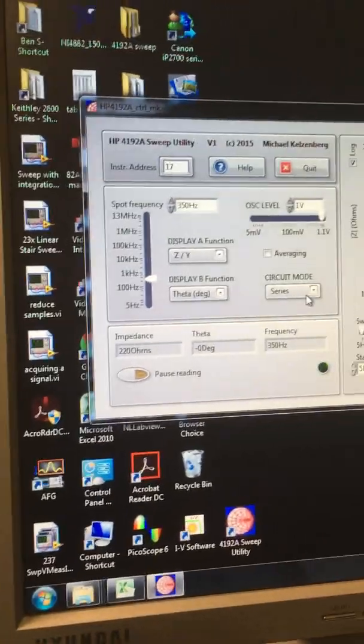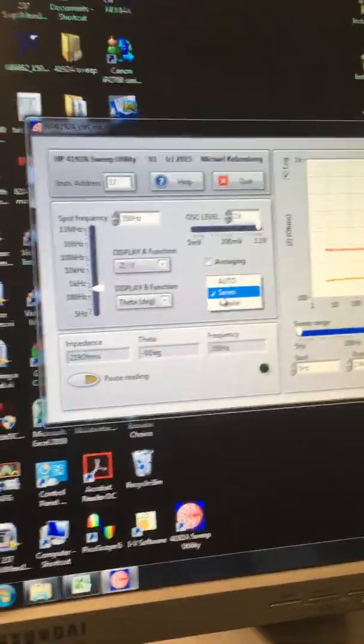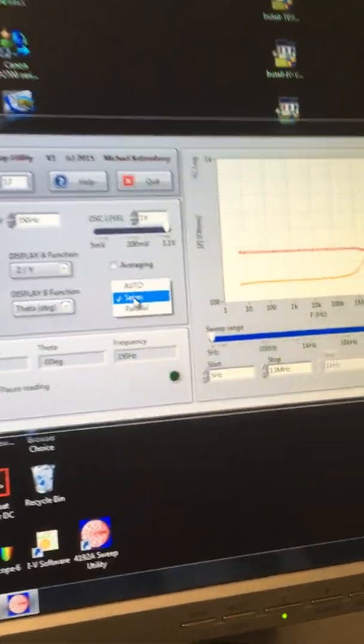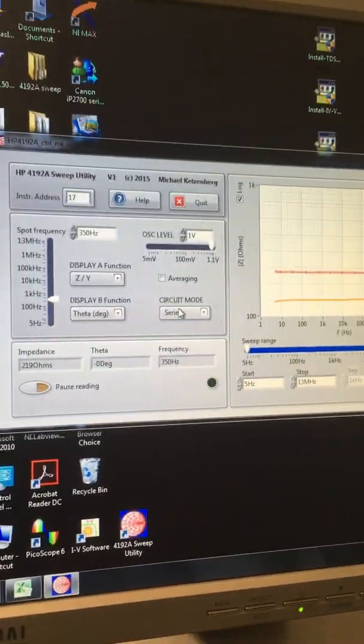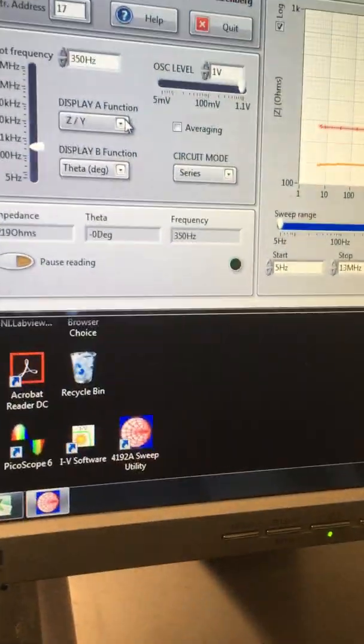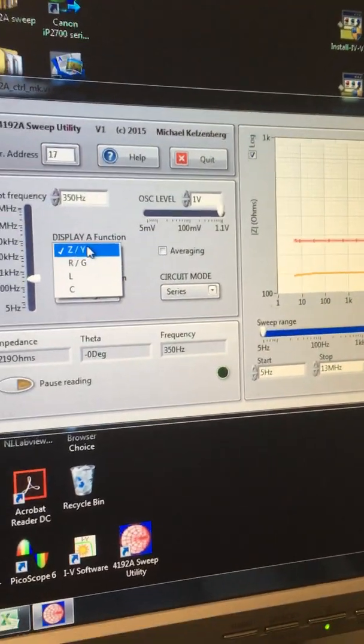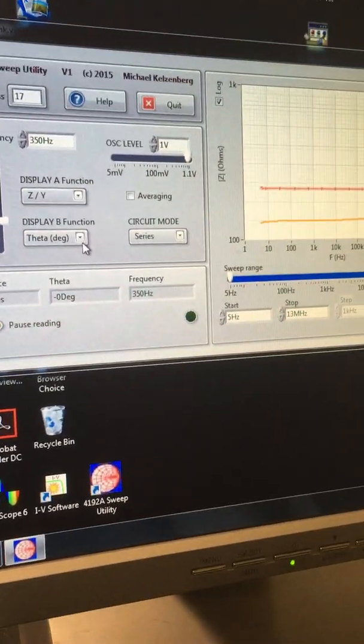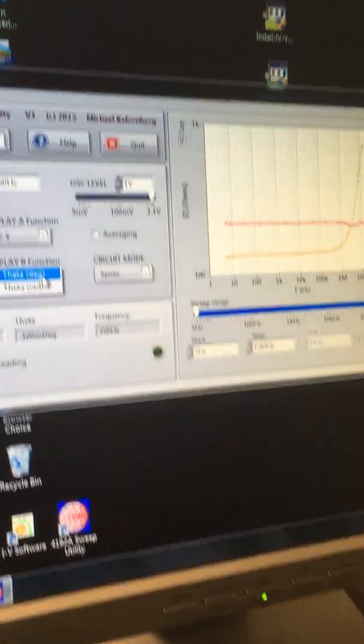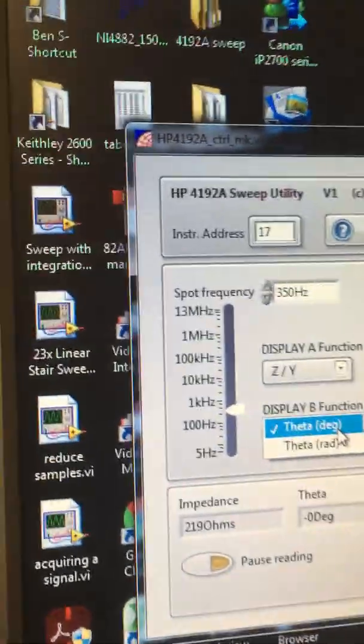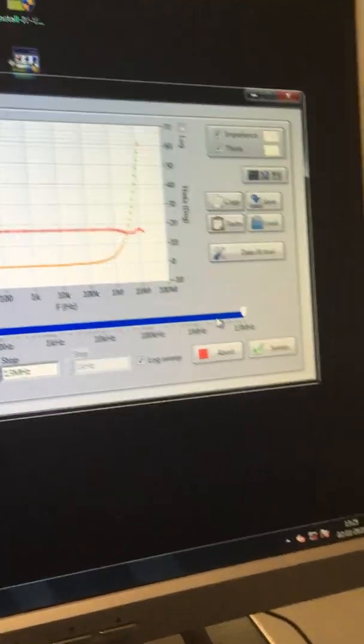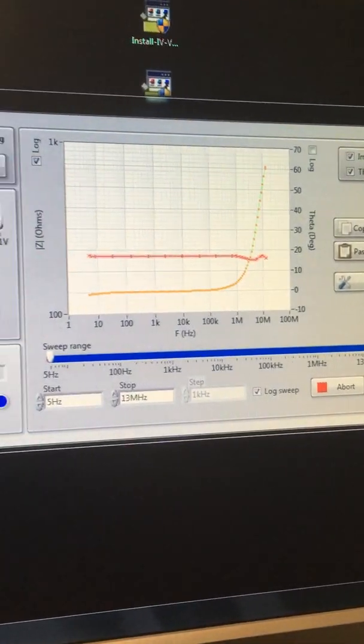This is the circuit, so we probably want to use series here. We've probably got basically this device as just a resistor which is in series. The display function is on Z—that's the impedance—and then we get the phase angle. I'll put that in degrees. Once that's set up, then you just click sweep.